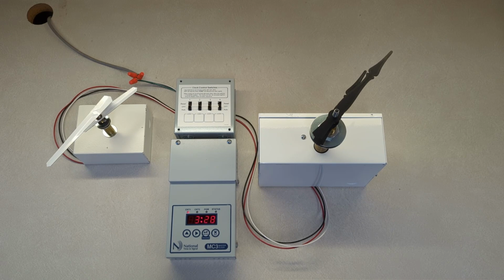Now that the time on the MC3 is correct, we need to get the secondary clocks on time. Notice the state of the LED labeled Circuit 1 on the MC3. If the LED is on solid, the clocks are in normal run mode. If the LED is off, Circuit 1 is turned off. If the LED is blinking, that means a reset is currently in progress. If this is the case, you will want to either let the reset finish or cancel the active reset by turning Circuit 1 off and back on again.